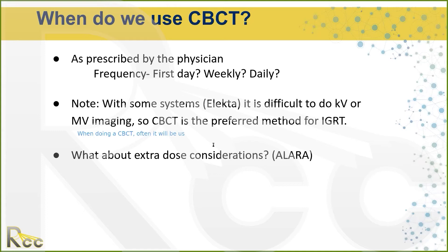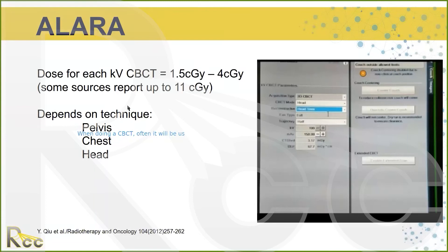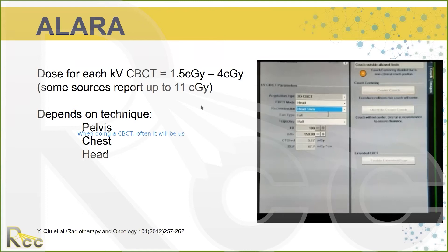It's a great verification and it's very minimal dose — which brings me to ALARA: as low as reasonably achievable. Cone beam does give more dose than KV images because one cone beam consists of like 600 to 1000 KV images. KV images give doses in the milligray range, so cone beam doses are a lot more. This paper talked about doses in the 1.5 to 4 centigray range, but it might be higher, more like 10 centigray.